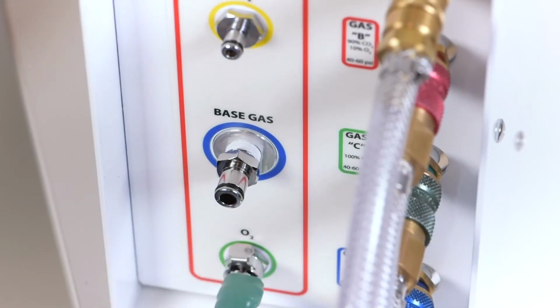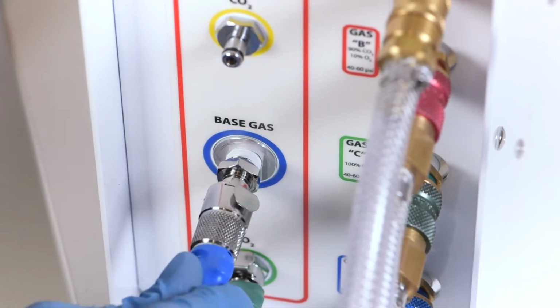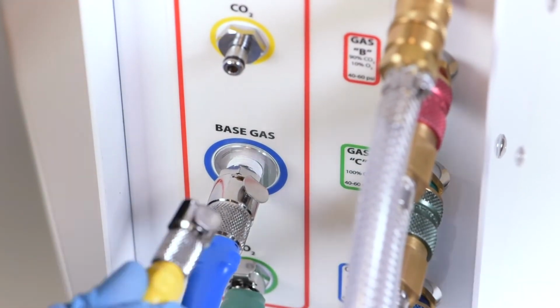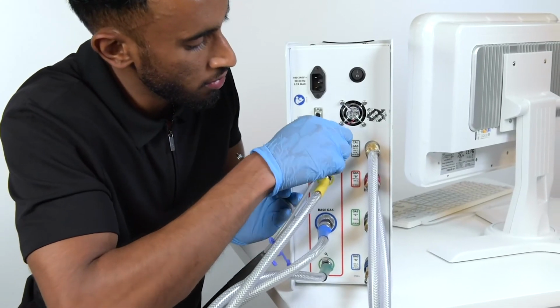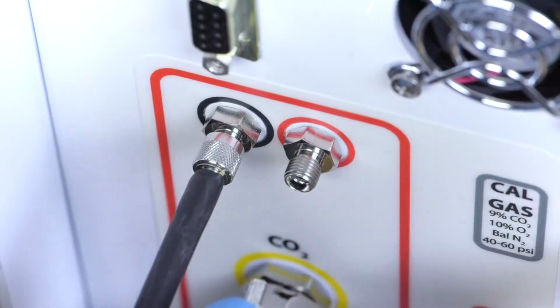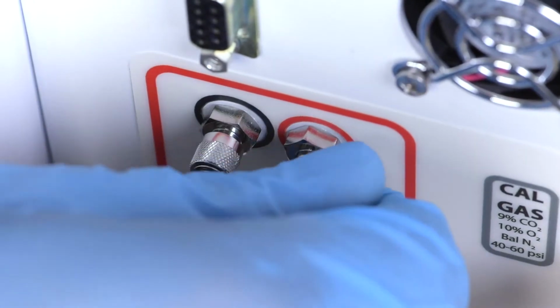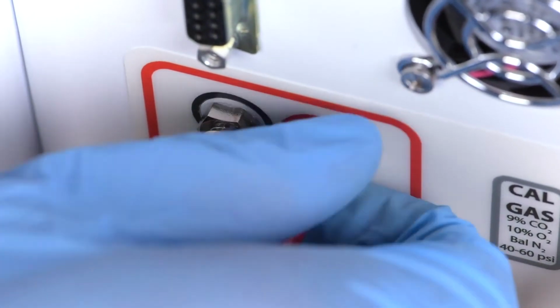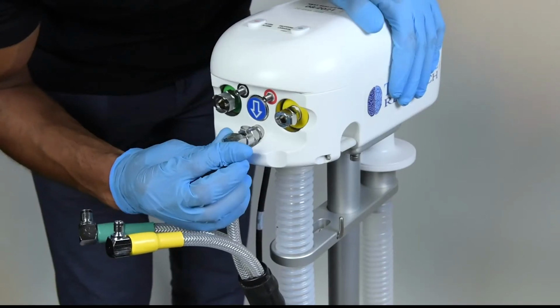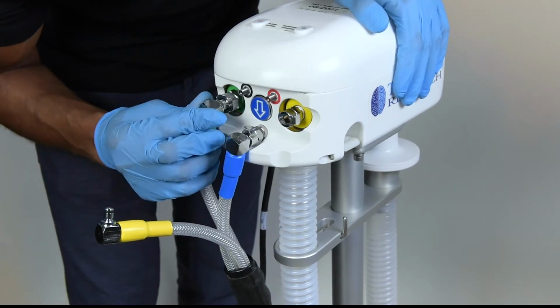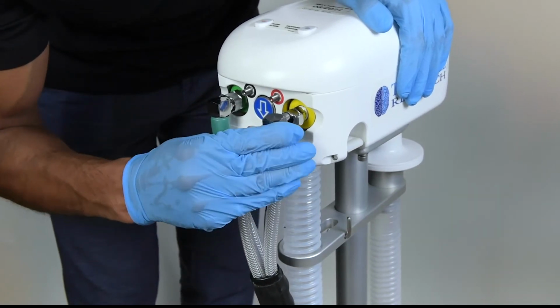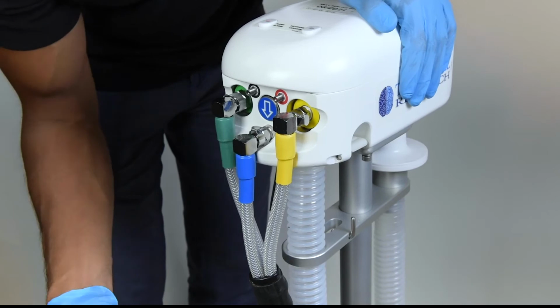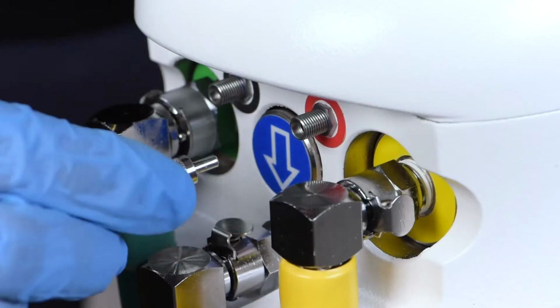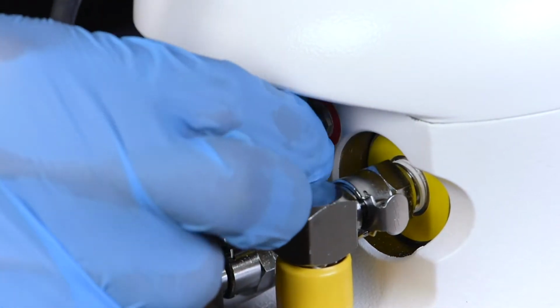Next, the hose fiber bundle can be connected to the input connections on the left-hand side on the back of the control room unit. Ensure to connect the gas input hoses first and the fiber optic cables last to prevent added strain on the fiber optic cables. Take the other end of the hose and fiber bundle and attach it to the MRI unit. Again, ensure to connect the fiber optic cables last to prevent added strain on the fiber optic cables.